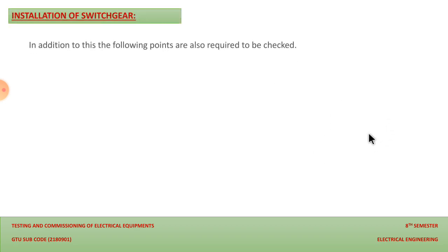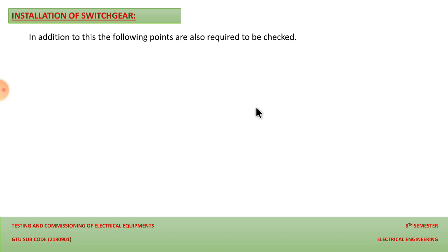And in addition to the installation of the circuit breaker, there are the following points that we should check before we connect our device with the system. First is the location where we are installing our circuit breaker. In the previous section we discussed the handling portion, and now this is for the installation purpose. So for installation, the location must be checked. If contaminated air and moisture are present in the air, you should check that before you install your device at the consumer premises.